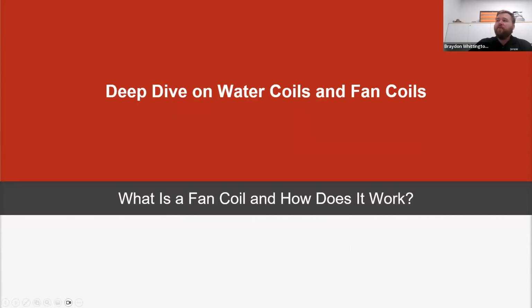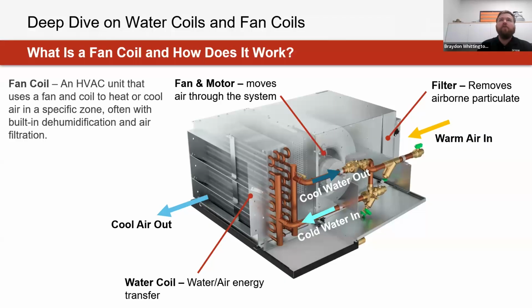For sure. Yeah, and I've seen some responses here too. For some it's a part of their day-to-day, some see it come up occasionally. But I don't want to assume anyone's background knowledge, especially if this is the first time ever seeing this equipment or learning a little bit more about it. Essentially, at a simple level, you've got a fan and a coil, where the fan is pushing or drawing air through the coil before it's delivered to the space. A lot of the time it's going to be provided with a cooling coil, and more typically, I'd say in terms of attachment rate, 95% of the time, a heating coil as well for supplemental heat. But essentially that's what's going to be providing some cooling or heating to that occupied zone when paired with this equipment.